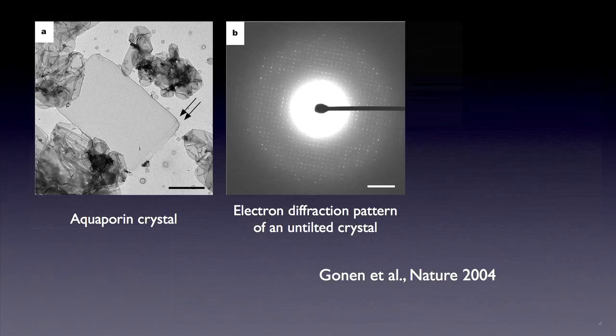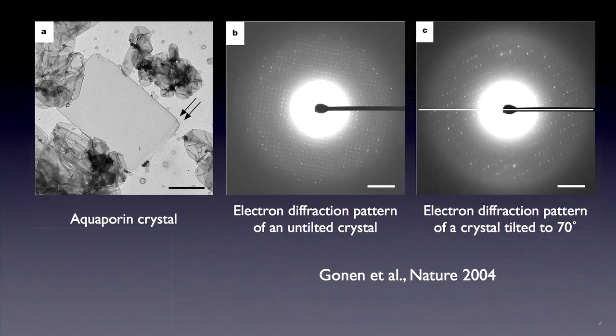But in addition to the images, it's advantageous to record a large number of diffraction patterns as well. Here's an electron diffraction pattern recorded of a crystal in an untilted condition. You see all the discrete spots. The intensity of each spot can be measured directly, and its square root is the amplitude that's needed. When recording diffraction patterns, to protect the camera, we insert a beam stop to block the unscattered beam because it's so intense.